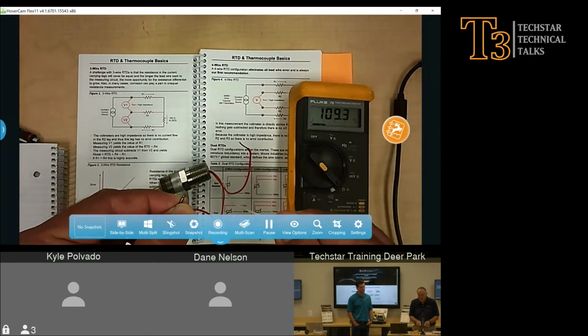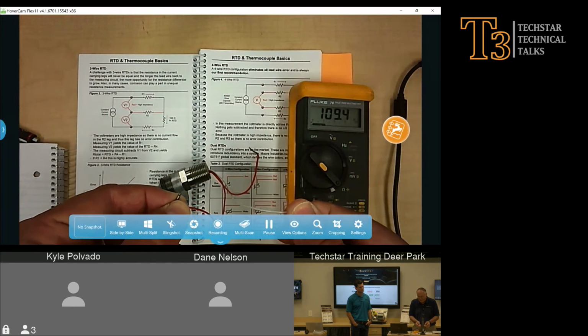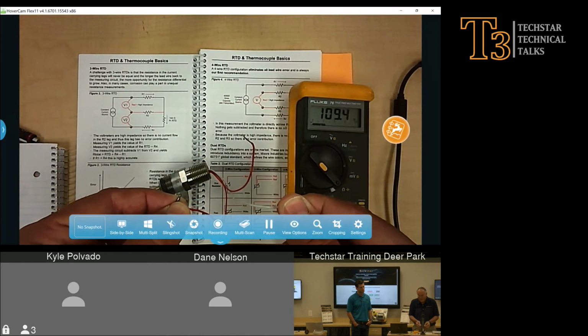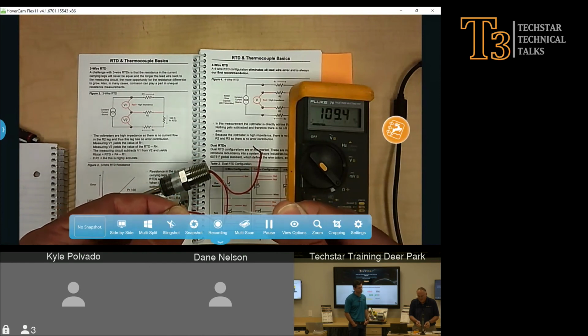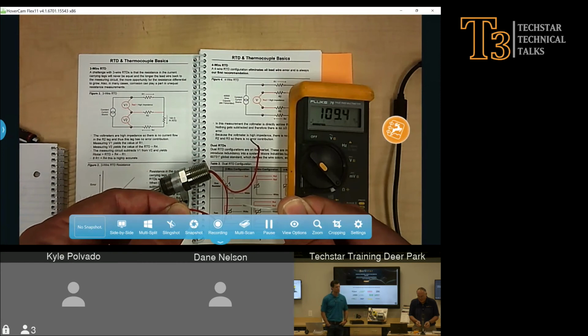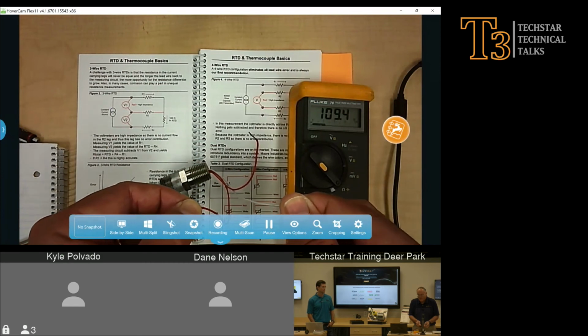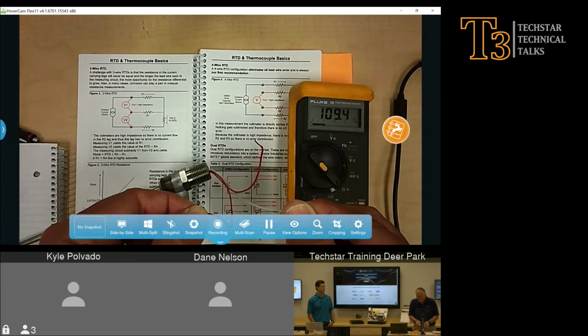Well, at ice point it is 100 ohms. So we'll talk about how to read the chart. This says 385 alpha, and that's ohms per degree C. So at ice point, I have 100 ohms. I multiply it by 0.00385, so that gives me a value of 0.385. So that means for every 0.385 ohms, that's 1 degree. So if we calculate it out, it's probably low 70s here.